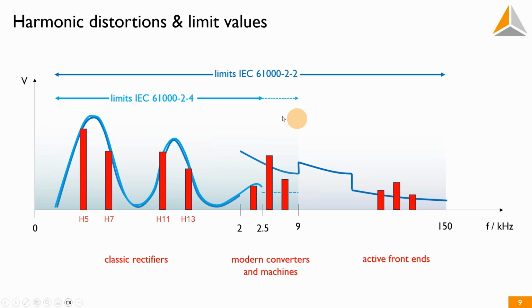So that's why, again, my recommendation for the first step, go with a standard which covers the whole frequency range, for example, the 2-2. And now you're good to go and see all the disturbances, and you can evaluate against limit values. So without this evaluation, we wouldn't have been able to say, well, you have a problem with the 28 kilohertz.